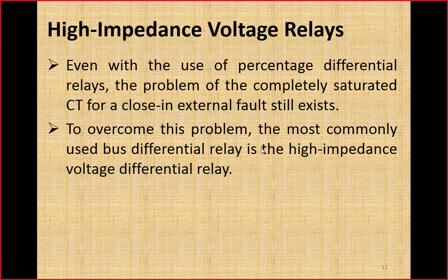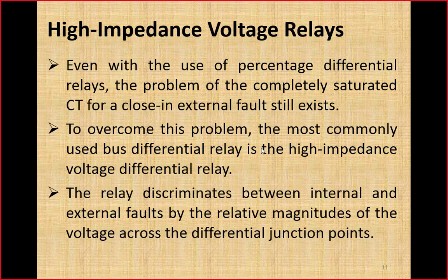This is the voltage that is to be measured in order to detect a fault, whether it is on the bus or outside the bus protection, instead of the current. This relay discriminates between internal and external faults by the relative magnitude of voltage across the differential junction point.